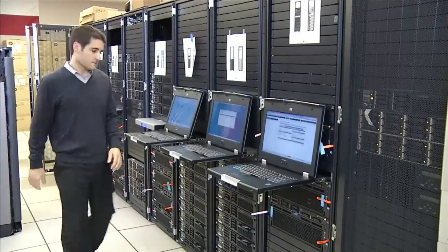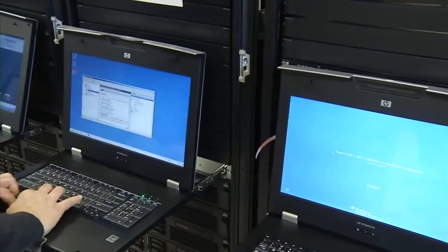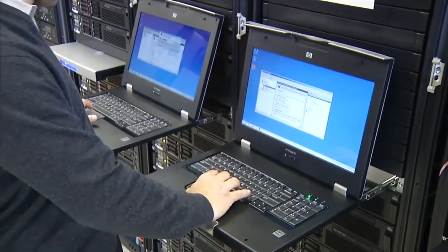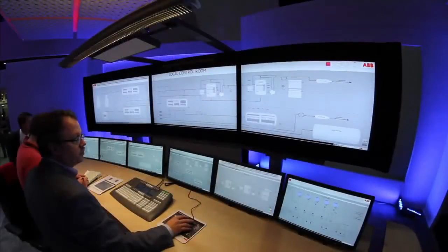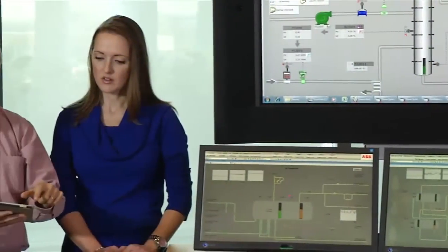The hardware that runs a virtual machine could be located in their own room or building far away from the control room. With virtualization, multiple automation system functions can run on the same physical computer as the virtual machines. The virtual switches provide the connections between these virtual machines as well as the physical network. Operators can still interact with the automation system through regular workstations or virtual clients.